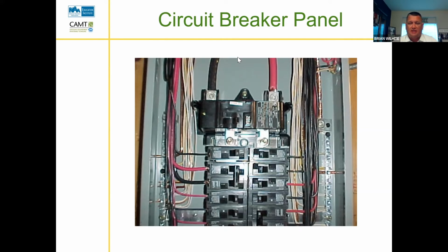So when you walk in, you're looking at this panel. I'm taking my leads and I'm putting my voltmeter on, and there's a setting for like 200 amp or 200 volts or 600 volts. I usually put mine at 600 volts because we're dealing with a little bit higher voltages here. And I put one of my leads on that top right red and my top left black. It doesn't matter which black and red on my meter goes there. It doesn't in this case. And I get a reading. And if it tells me I have 220 volts or 240 volts, then I know I have two separate legs of 120 volts.